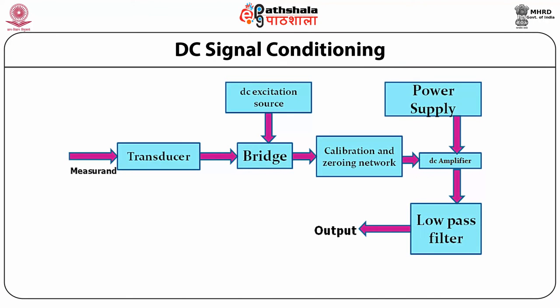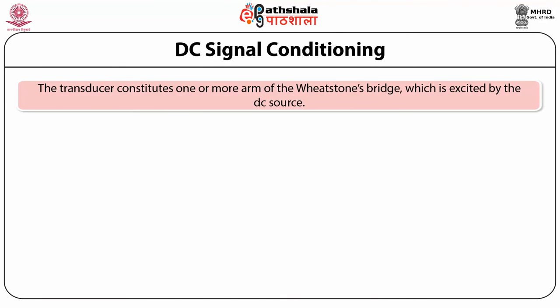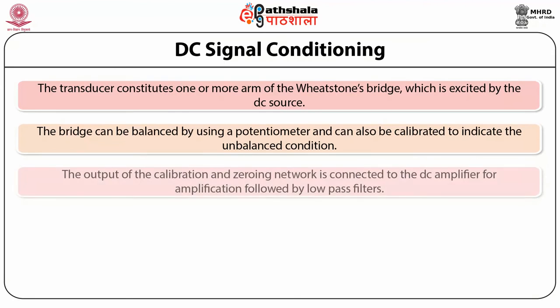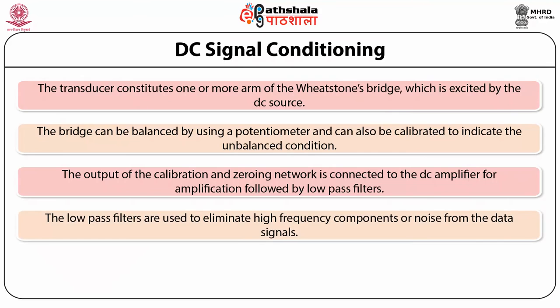DC signal conditioning: this block diagram shows the DC signal conditioning arrangement. Here, the transducer constitutes one or more arms of the Wheatstone's bridge, which is excited by a DC source. The bridge can be balanced by using a potentiometer and can also be calibrated to indicate the unbalanced condition. The output of the calibration and zeroing network is connected to a DC amplifier for amplification, followed by low-pass filters, which are used to eliminate high-frequency components or noise from the data signals.